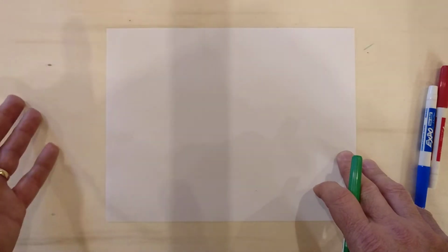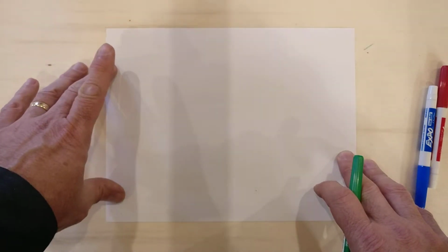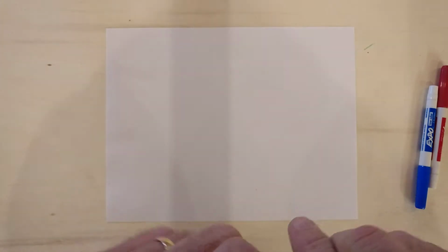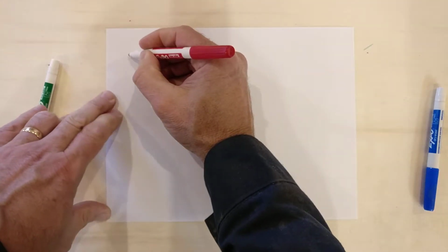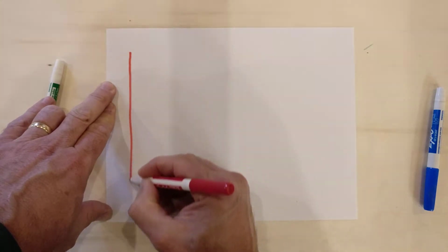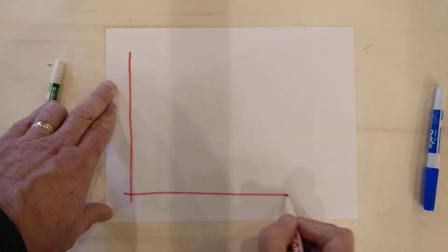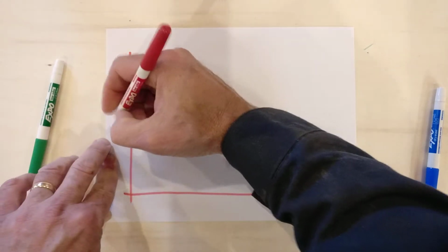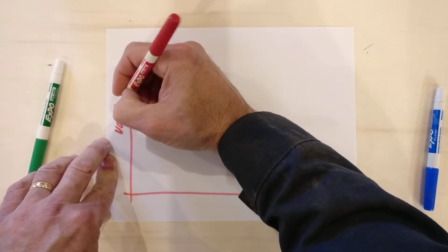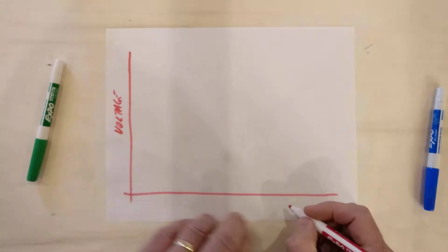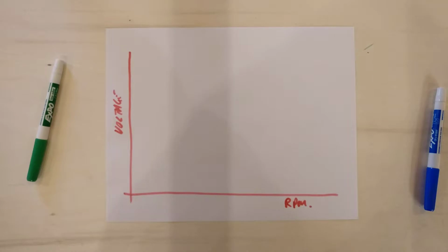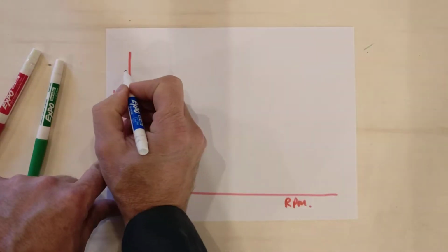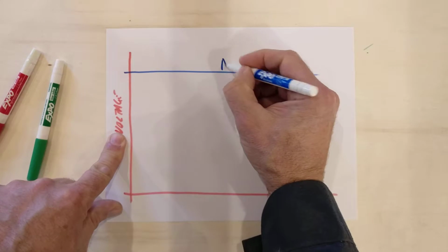Now, the way we underspeed a motor is we reduce the applied voltage to the armature. If you recall, I'll draw it again here, that the motor will always tend to run at a point where the applied voltage is, or at least the counter EMF is close to the applied voltage. So if I draw my little graph here, this side of the graph was the voltage, and this side of the graph is the RPM of the motor. And we had an applied voltage that was a fixed value, and it was just sitting up here somewhere. There's the applied voltage.